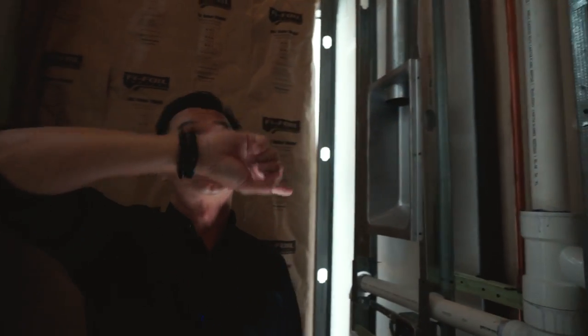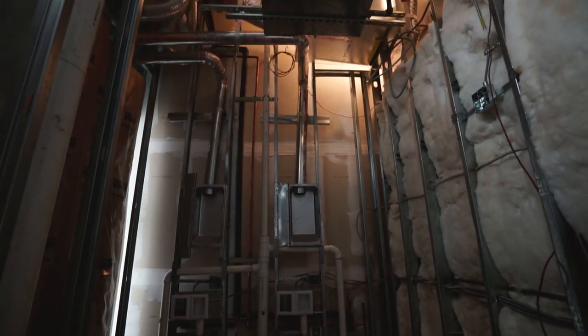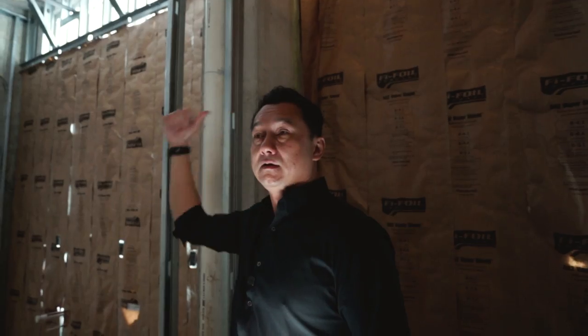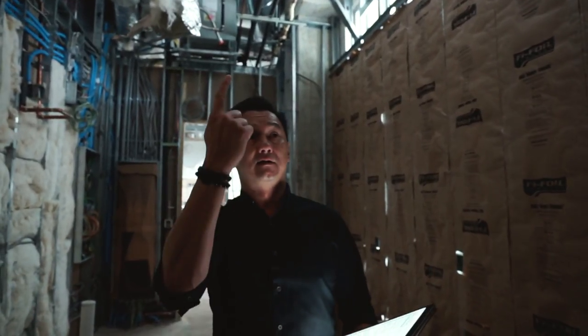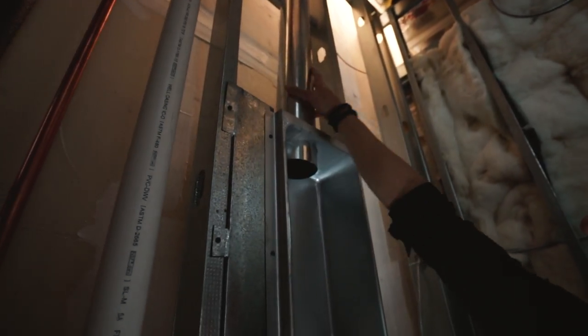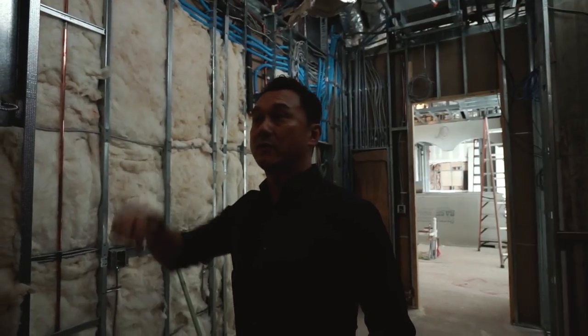Some of the other salons we have, this dryer vent goes all the way straight up. If there are multi-story high rises on top, the city code would not allow us to vent outside — it wants us to go all the way straight up to the ceiling, which could be 30 to 40 feet up and then go sideways to come out. With all the lint from the towels and dryer, even with an outside exhaust fan, there's always a problem. You can't clean the pipe — lint builds up year after year, causing condensation that then starts leaking into the salon. That's where the water comes from.